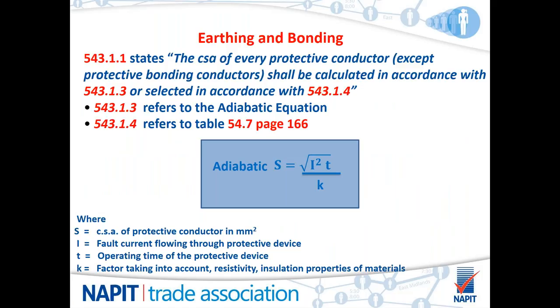The cross-sectional area of every protective conductor, except bonding conductors, shall be calculated in accordance with two regulations within Chapter 54 of the regulations. 543.1.3 is a regulation referring to the adiabatic equation, and the following regulation, 543.1.4, refers to Table 54.7 on page 166, the table that we will discuss in a while. In the blue box, you can see the adiabatic equation. All protective conductors are sized on this to ensure that they will withstand fault currents and therefore not melt like a fuse does before the fault has cleared by the protective device.